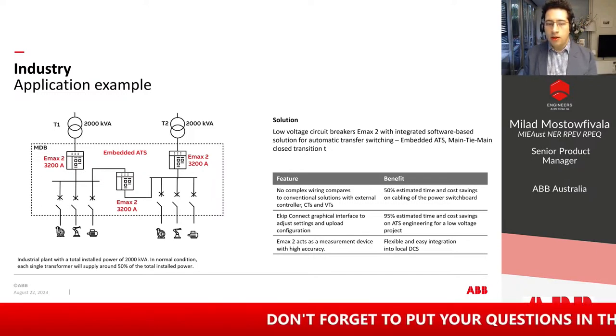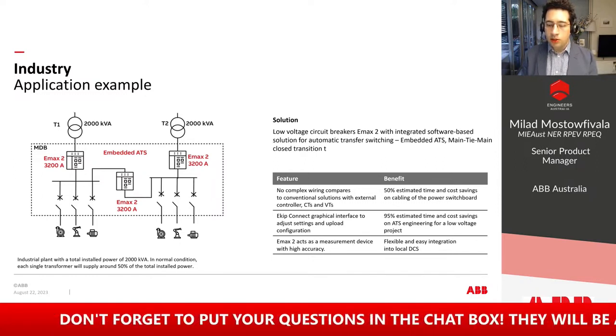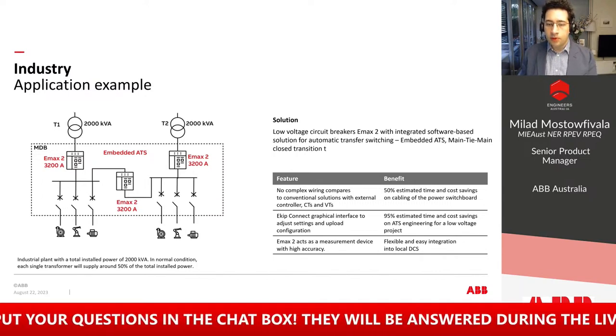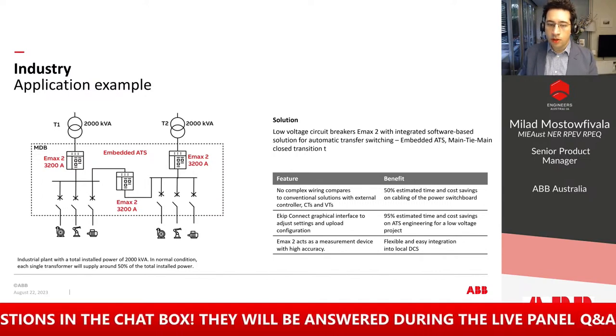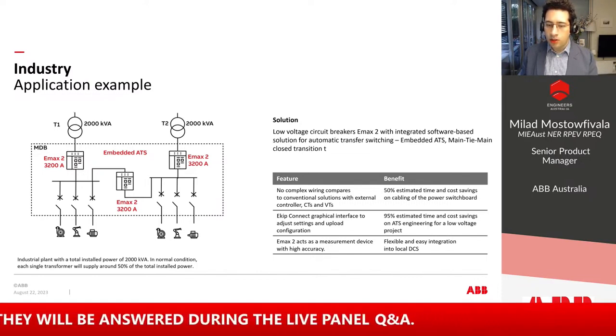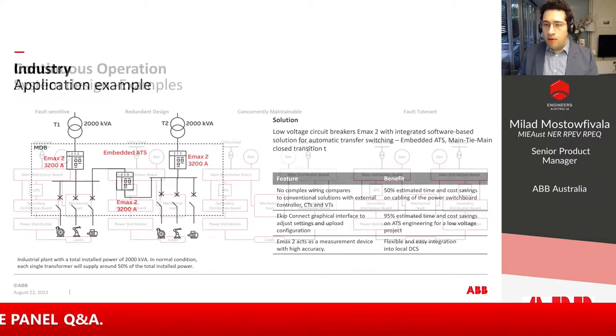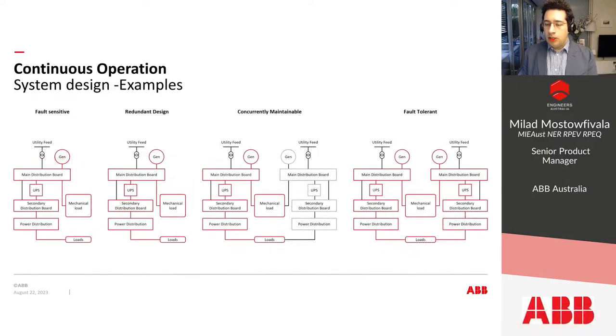There was quite a complex measurement and communication involved in this project, and with the use of the embedded circuit breaker based automatic transfer solution, they thankfully avoided the installation of CTs and VTs, measurement and analytics, and separate communication or protocol converters, and they were able to communicate to the local control system quite seamlessly with this design. So that was the case with our application reference design.